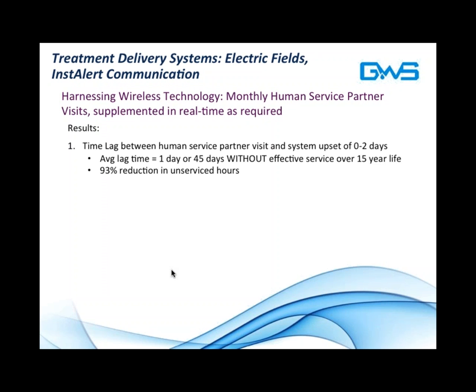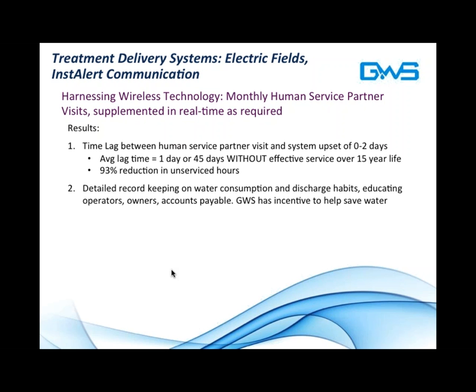Here's the upshot of that. First of all, lag time between human service partner visits is now 0 to 2 days. On average, let's say 1 day. So if you have 3 system upsets on your tower per year, which is inevitable, according to the chemical service partner experts, that means over the 15-year life of the tower, that's 45 days without effective service life. That's a much different result than 675 days under chemical treatment. That's a 93% reduction in unserviced hours.